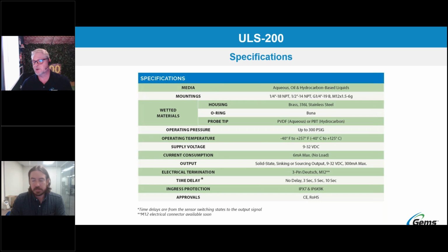Want to run through the specifications. We talked about the media that could be sensed. We talked about the mounting options and the housing. There is a seal O-ring and it is a Buna O-ring. The probe tip materials are either PVDF, that's for the water-based, or PBT, which is for the hydrocarbon or oil-based liquids. The operating pressure, a very high pressure rating up to 300 PSI.